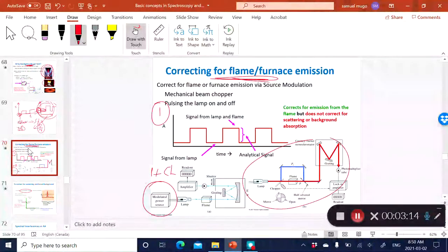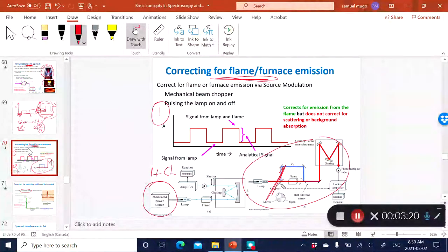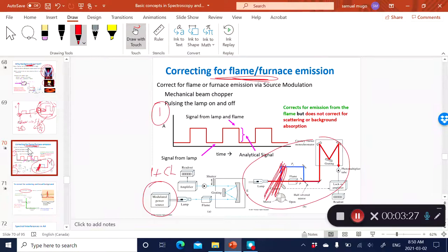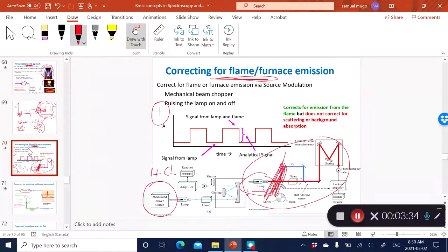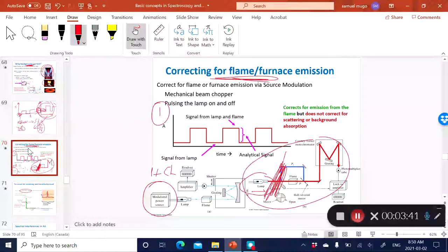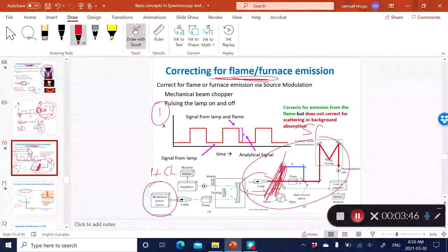Another approach to modulation is where you use a beam chopper, which is able to block the light from the flame. At one point, you block the lamp from getting to the flame, so the detector is only detecting the signal from the flame — meaning just the background.